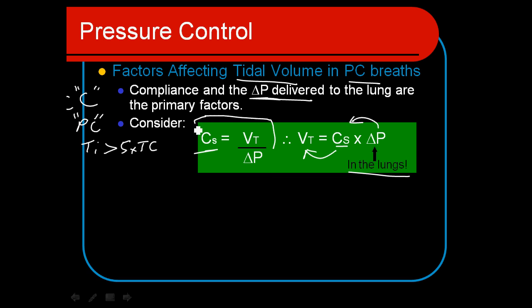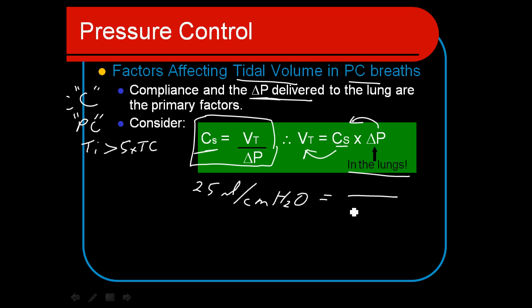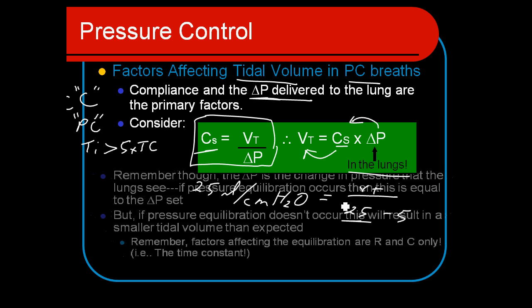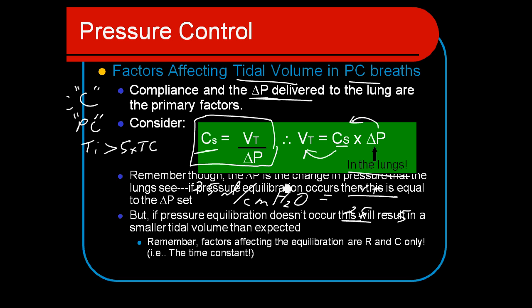This equation is important to know. For example, with a patient compliance of 25 mL/cmH₂O, a pressure control of 25 with a PEEP of 5 gives a delta P of 20 — from this you can calculate the expected tidal volume. However, this depends on equilibrium occurring. If pressure equilibrium doesn't occur due to insufficient TI, the result will be a smaller tidal volume than expected, and we won't know exactly how much pressure is entering the lungs.